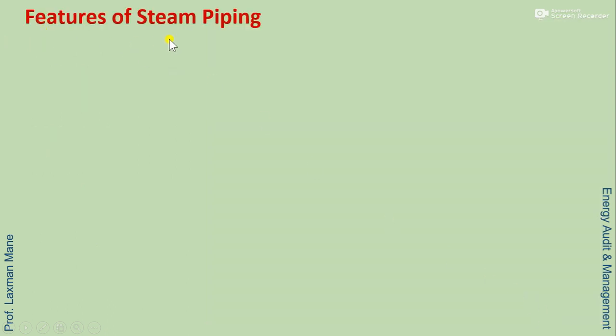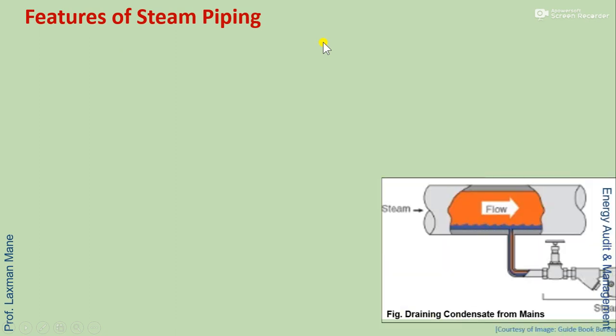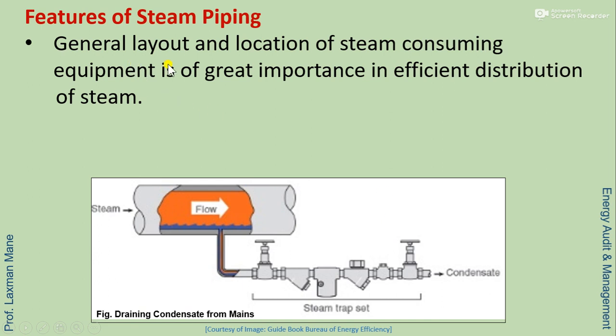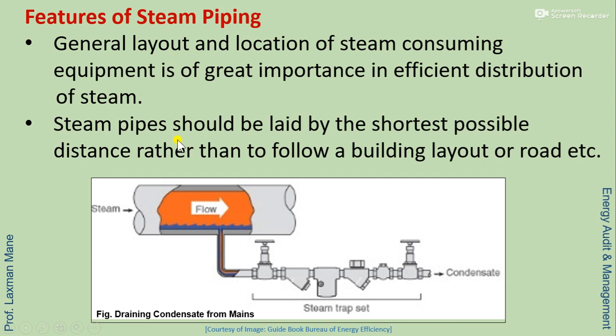Features of steam piping: here is a diagram of the steam piping general layout. The location of steam consuming equipment is of great importance in efficient distribution of steam. Steam pipes should be laid by the shortest possible distance to avoid frictional losses, rather than following a building layout or road.